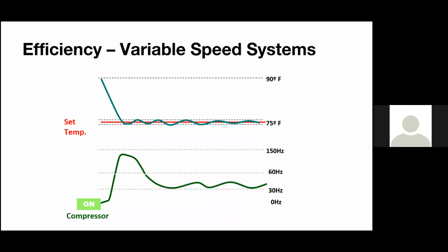We're looking at 95 degrees there, right? So let's say we have a home and we need 4 tons for a conventional system. All right, that's good. But what happens when it's 70 or 65 degrees outside? We might need a little cooling capacity. So what's going to happen is that conventional piece of equipment is going to cycle on, off, right? And it's still going to probably overcool the space, and it's just not going to be comfortable.